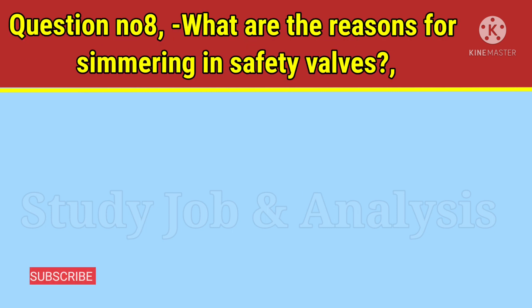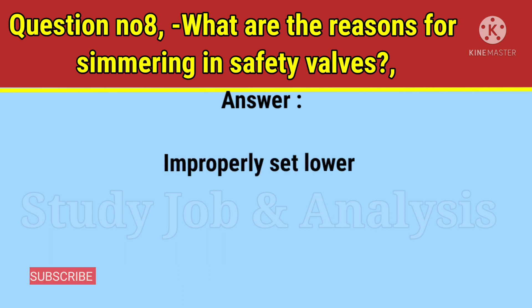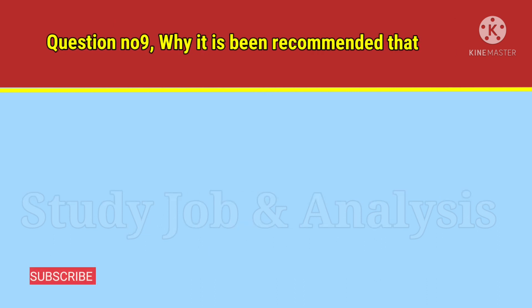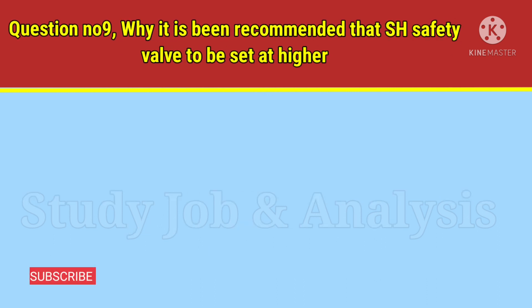Question number eight: what are the reasons for simmering in safety valves? Answer: Improperly set lower ring, holding the boiler pressure at or very near to the set pressure of the valve, and maintaining a higher drum level during lifting of the boiler safety valve.